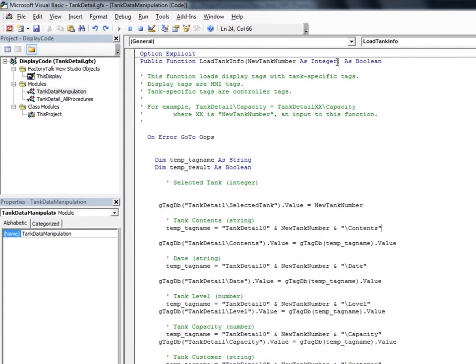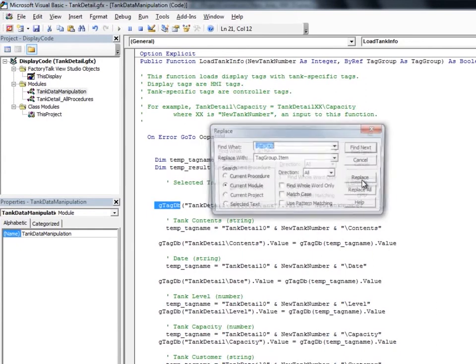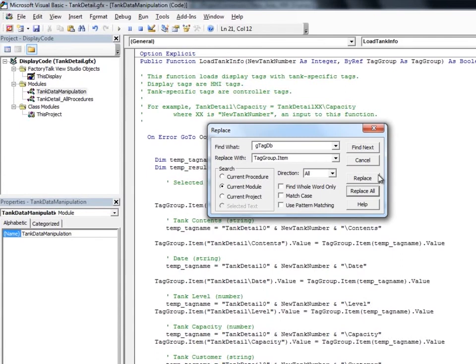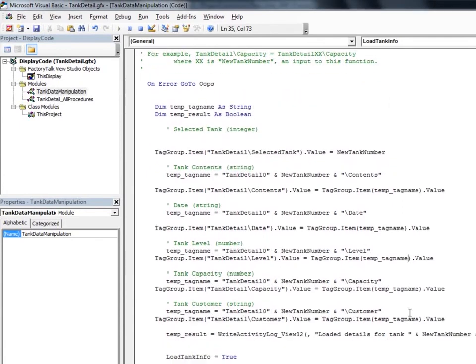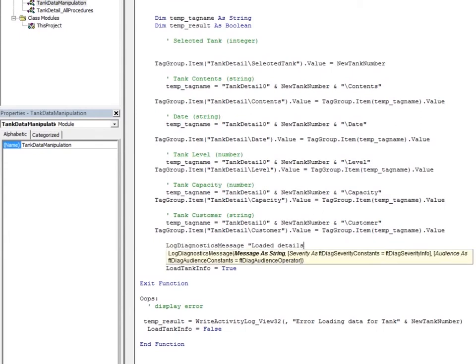First, we need to add a byref reference to the tag group in this module in order to be able to use it here. Next, we'll replace the gtagdb references with taggroup.item. And finally, we'll update the error handling to write to the FactoryTalk Diagnostics log.